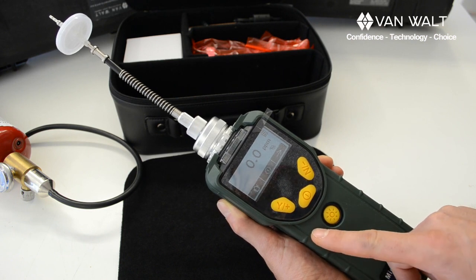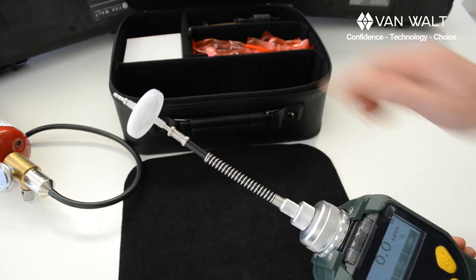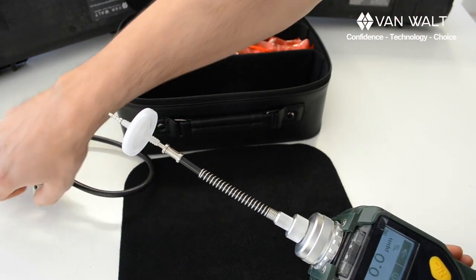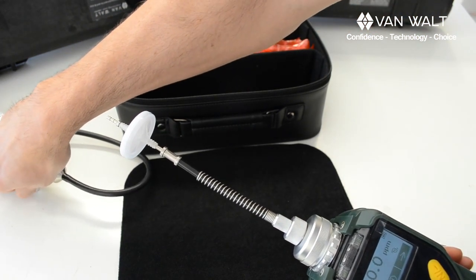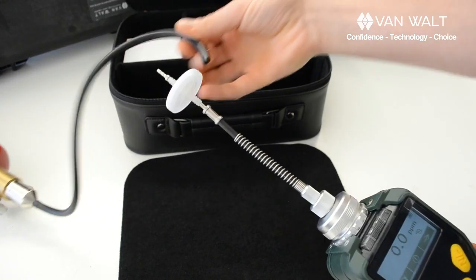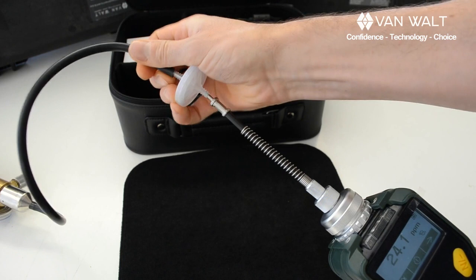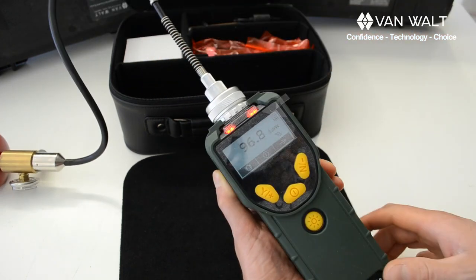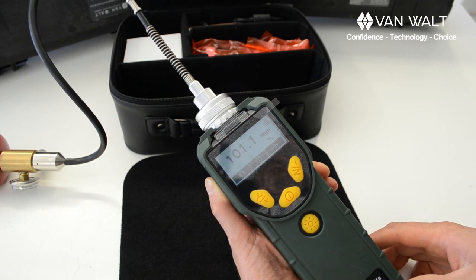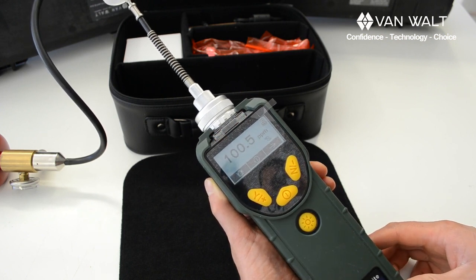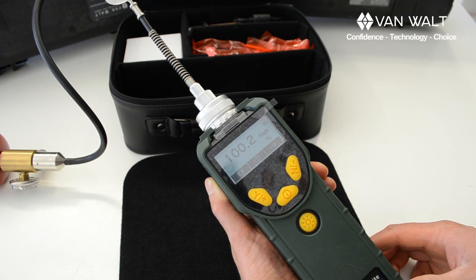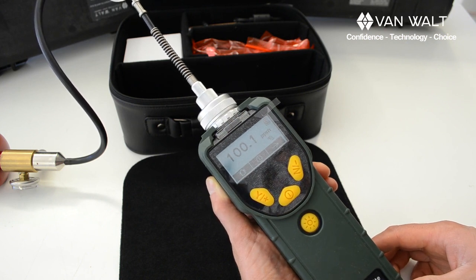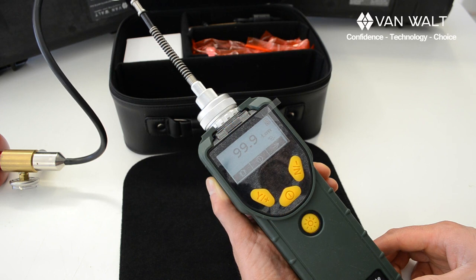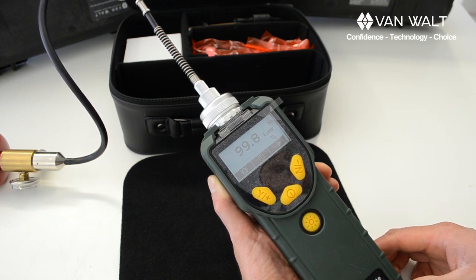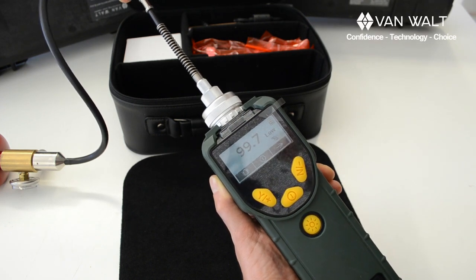And then to complete the bump test, we will give it some gas. So I've got a can of isobutylene at 100 parts per million, and we can fit that to the nozzle. And that's showing near as makes no difference, 100 ppm, which is good. Plus or minus 10% is fairly normal, but we find these machines are pretty good. They will hold a good calibration, plus or minus a couple of ppm, a couple of percent over a short period. I'll turn it off now.